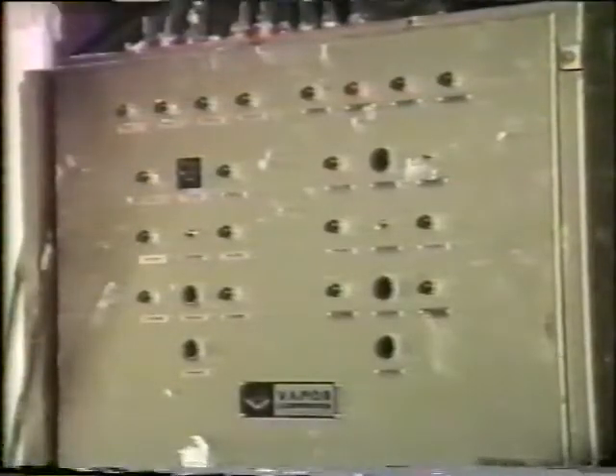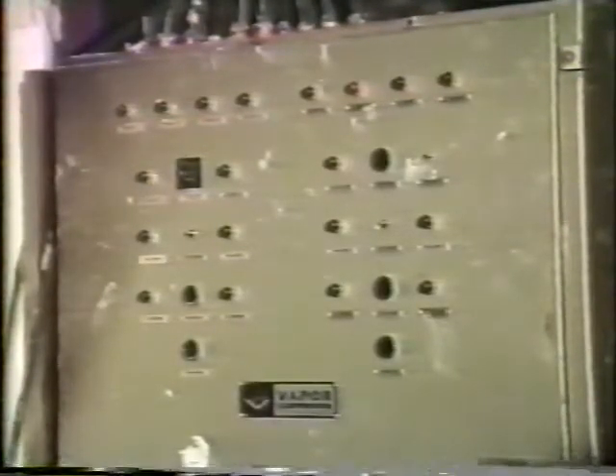Exhaust gas boiler operation. As stated in the introduction, the exhaust gas boiler is capable of dry running. However, this procedure should only be used in case of extreme emergency. Therefore, operators must be prepared to operate the boiler before the main engine is started. Startup.